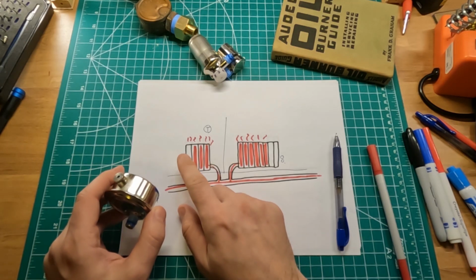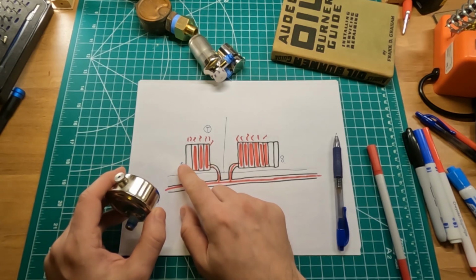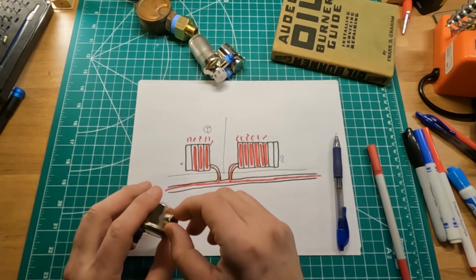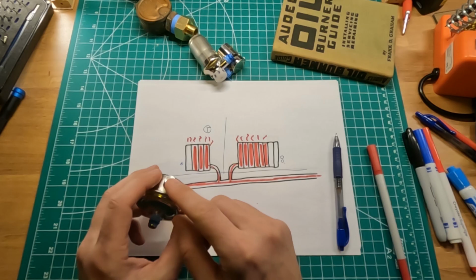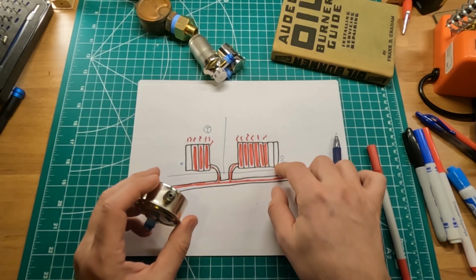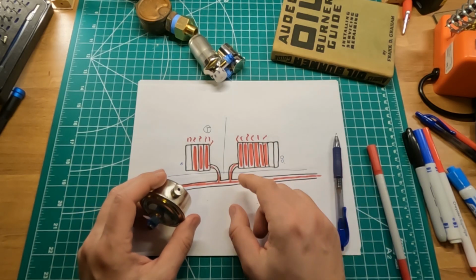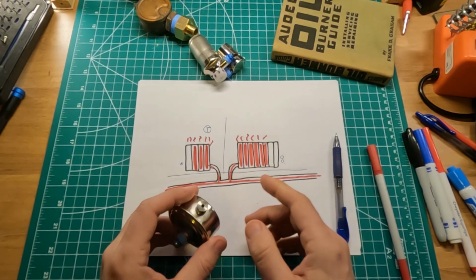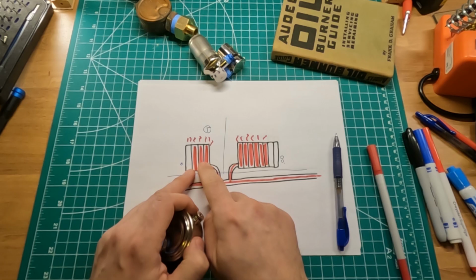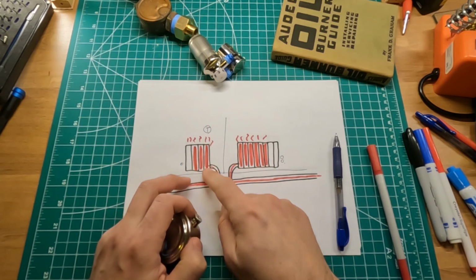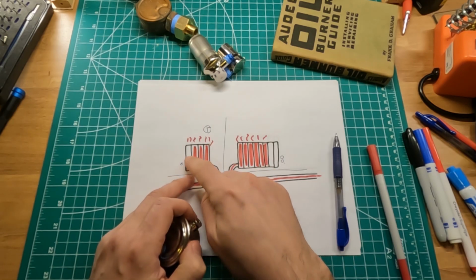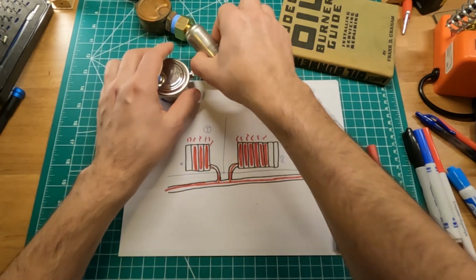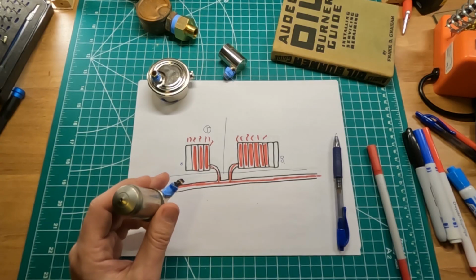The radiators that are closest to the boiler, again, that's all theoretically speaking, because that's not always that simple, you would put relatively small openings, and then on the radiators far from the boiler, you put relatively large openings. And then at the same time, you have to consider that obviously a smaller radiator will overall heat up faster with the same size of opening than a large radiator if the opening were to be the same one.